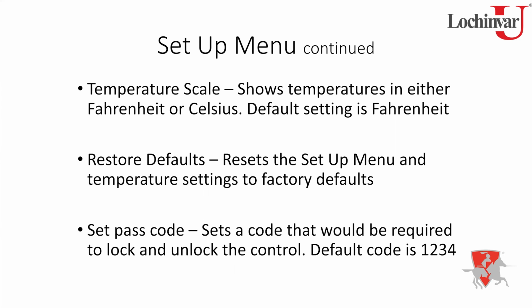Then you've also got the ability to restore the defaults. Now, again, not that many parameters here to restore, but if you just want to come in and put it back to factory settings, you can do that with the restore defaults button. Now, if you want to add that extra layer of protection to prevent people from changing things, we can come in and put in a passcode. Your default is 1, 2, 3, 4. Pretty simple if you activate it, but I would say if you're going to use it, somebody's probably going to change it, right?